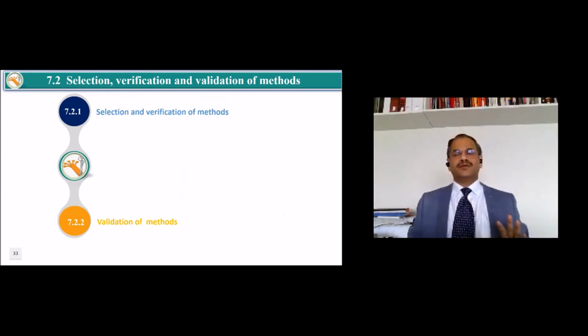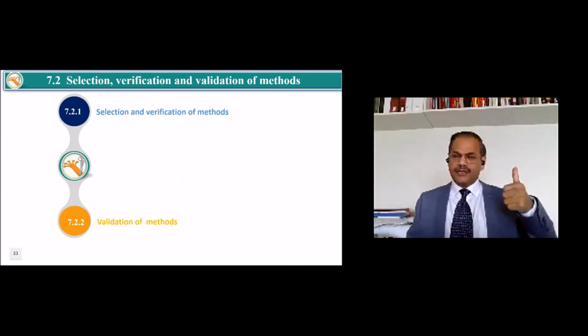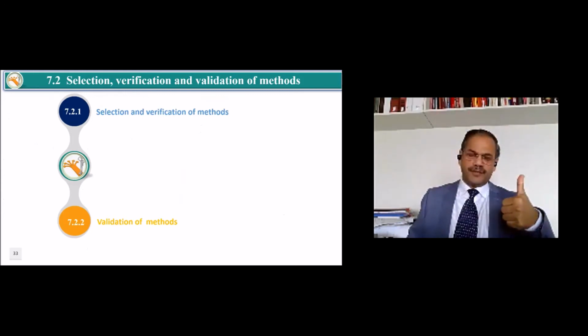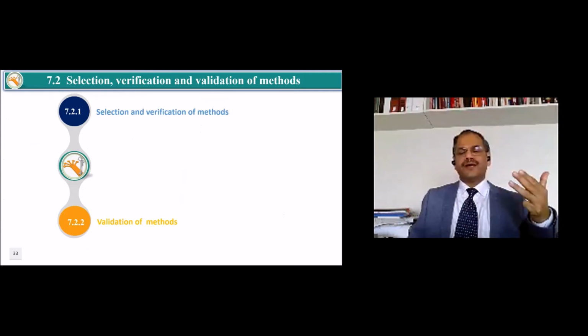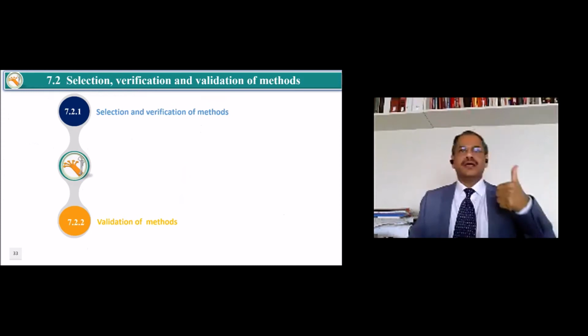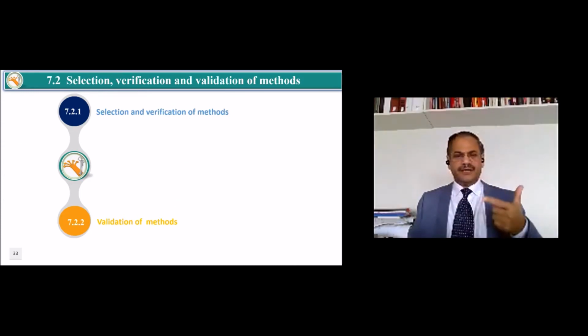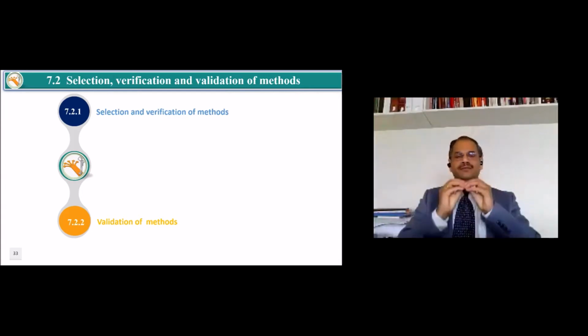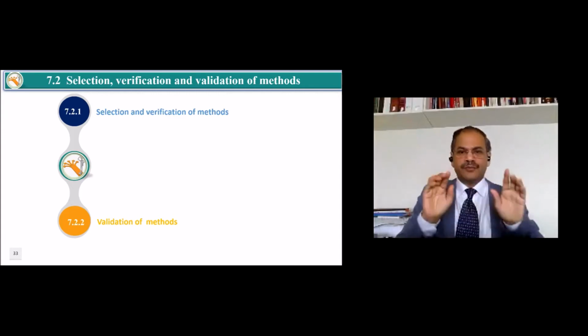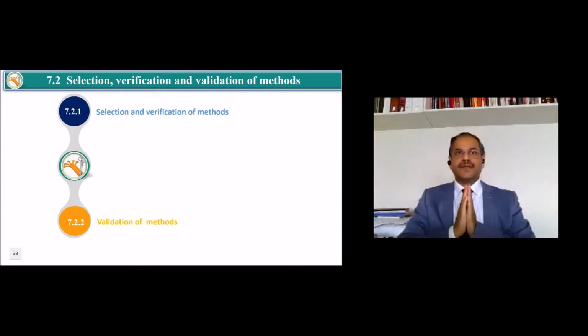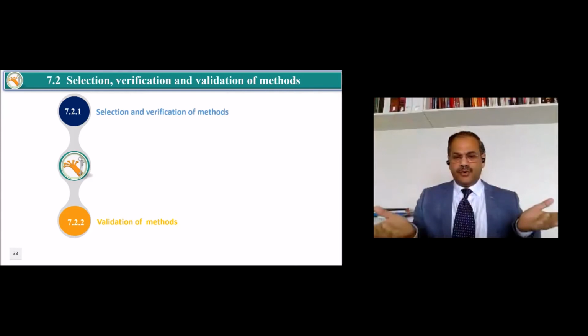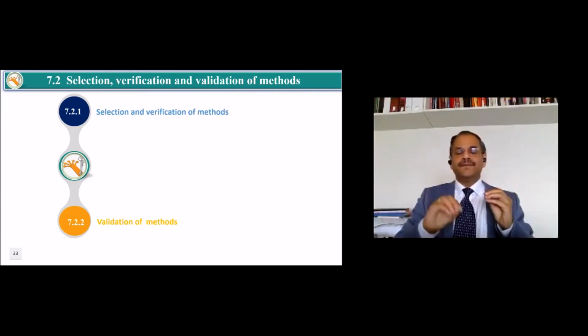What type of method you shall have? There may be 3-4 different types of requirements. Either you can have a contractual agreement, or there may be a legal requirement, or some regulatory requirements, or it is referred by some of the standards. So you may have the reference method, which is an internationally renowned method like ASTM, IP, DIN, IS. Or you may have your in-house methods. You have to verify all those standard methods which you are implementing in the lab to perform the test or calibration. But if it is an in-house method, as is mostly the case in DRDO or pharma, perfectly okay. You need to perform the validation of that method and then you can get an accreditation.